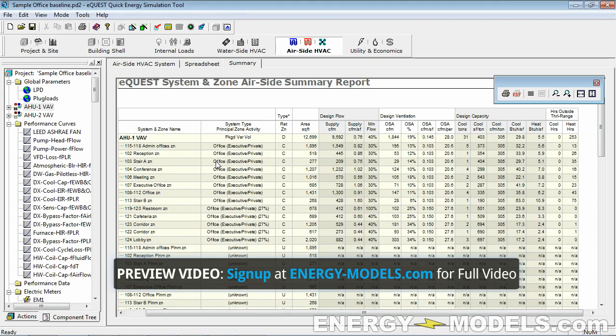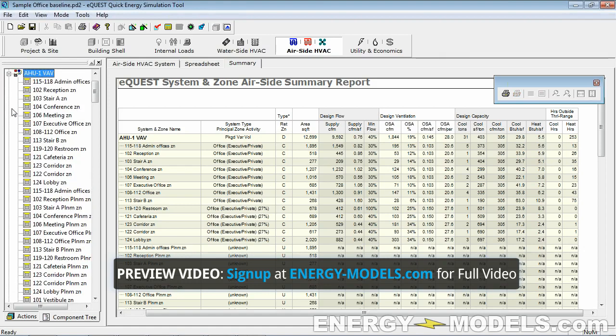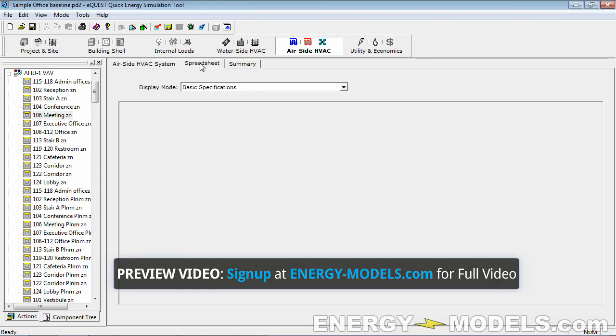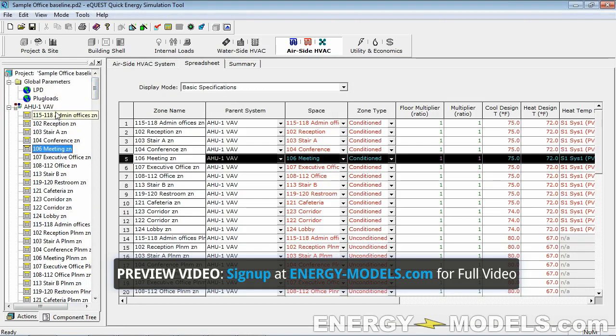It's typically just because it's a VAV system, and a VAV system has unmet hours because of the reduced airflow. Depending on the cooling-to-heating ratio, we hard-coded in 0.4 CFM per square foot, and depending on the ratio, that might not be enough based on the supply temperatures.